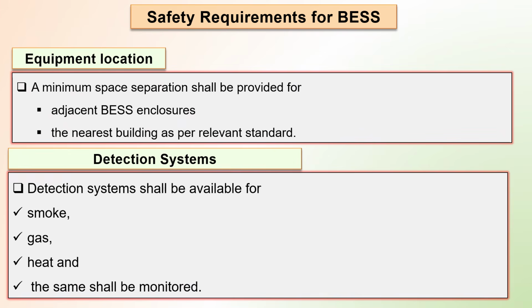Thereafter, the regulation states that for the equipment location, a minimum space separation shall be provided for adjacent BESS enclosures as well as between the BESS enclosures and the nearest building as per the relevant standards. Now, the list of relevant standards shall be notified separately by the Central Electricity Authority. Then there should be detection systems available for smoke, gas, and heat, and the same shall be monitored. So it is important to note that there shall be at least three detection systems for smoke, gas, and heat.